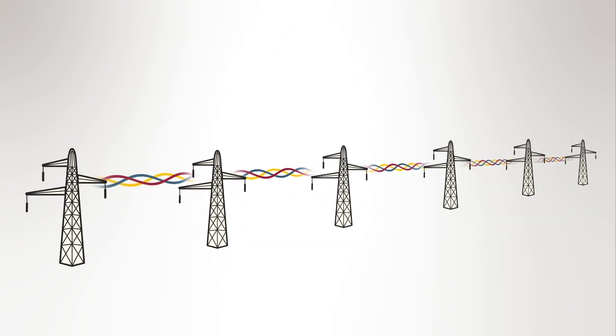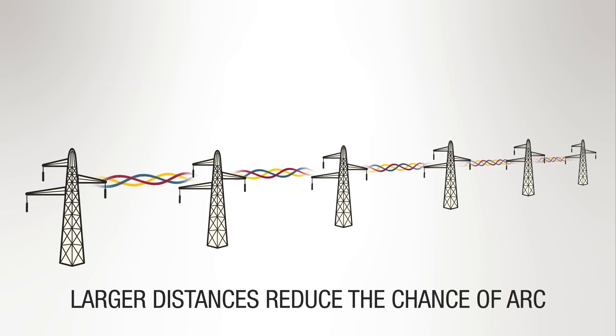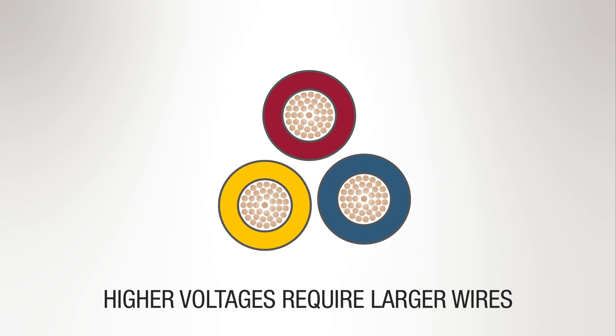A general rule of thumb is that 1,000 volts are required for each 1.6 kilometers or 1 mile of distance to move the power. Transmission voltages can reach over 700,000 volts. Higher voltages require larger distances between the phased wires to reduce the chance of an arc. Higher voltages also require larger diameter wires.